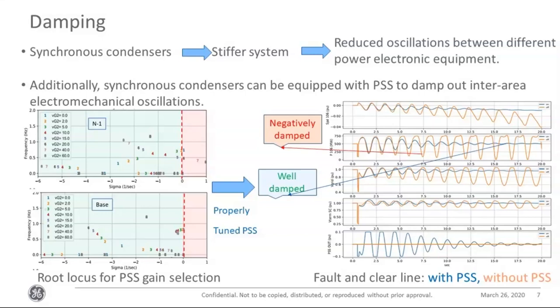But in the N minus 1 condition, which is the root locus on the top, you can see clearly that point 1 is on the right half plane, which means you're going to have negatively damped oscillations for that mode. But for about the same frequency, as you increase the PSS gain, you can see point 2, which is a gain of 2, has moved slightly into the left half plane. So that's reasonably damped. And then 3 and 4 is further damped.